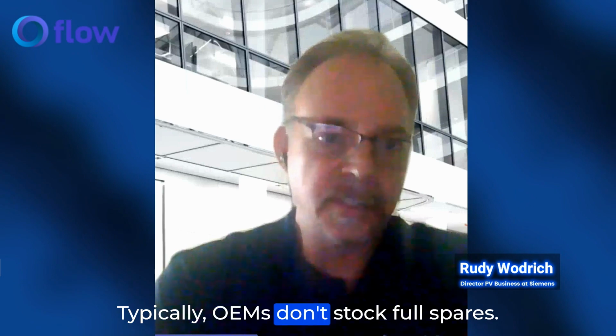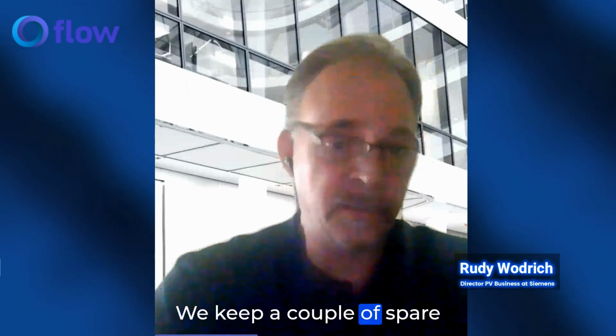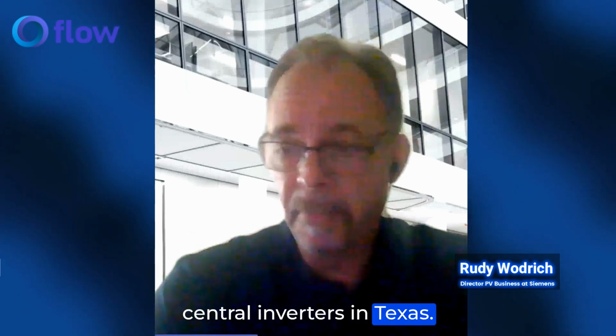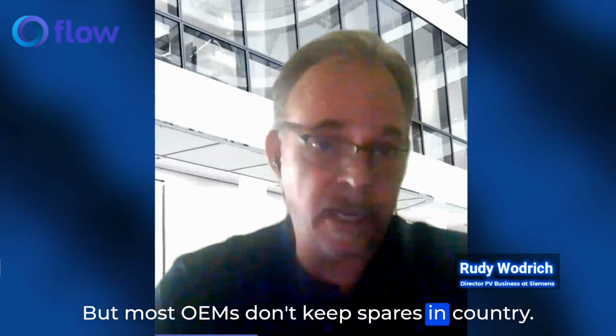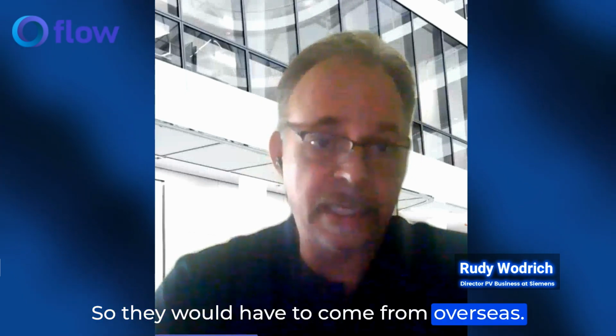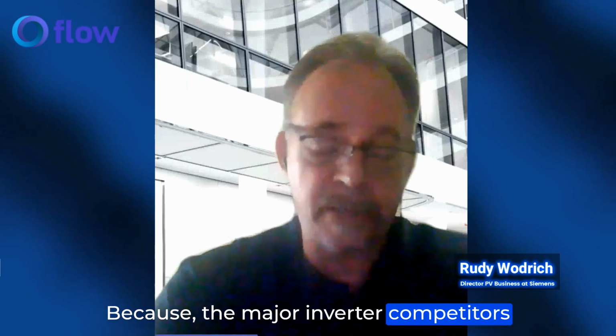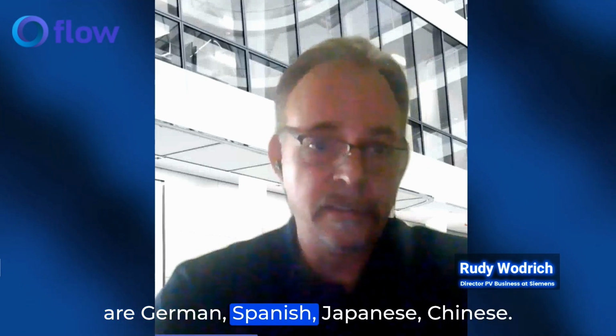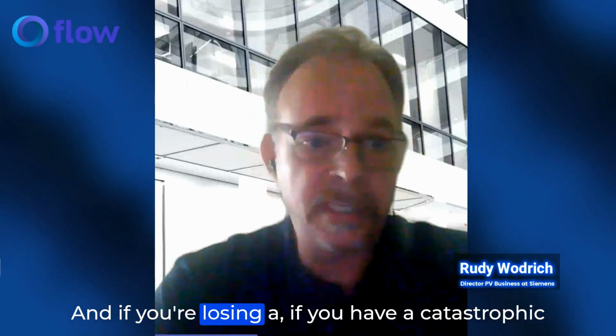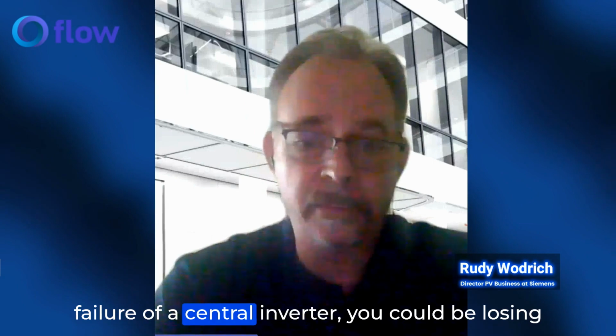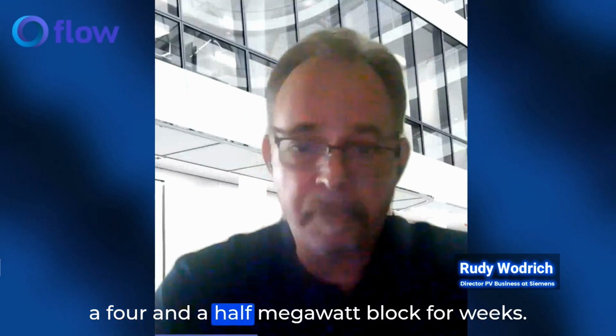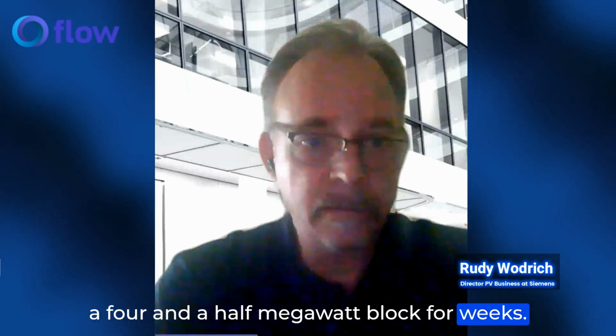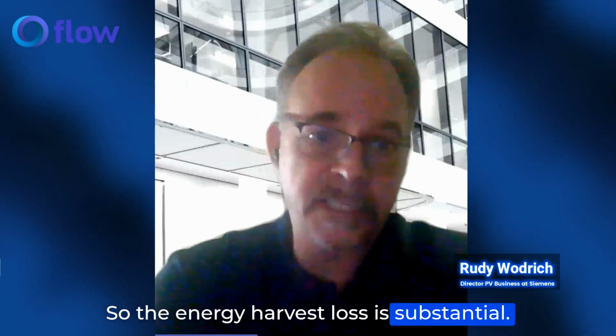Typically, OEMs don't stock full spares. We do. We keep a couple of spare central inverters in Texas, but most OEMs don't keep spares in country. So they would have to come from overseas, because the major inverter competitors are German, Spanish, Japanese, Chinese, right? That's where they're coming from. So, this is a factor. And if you have a catastrophic failure of a central inverter, you could be losing a 4.5 megawatt block for weeks, right? So the energy harvest loss is substantial.